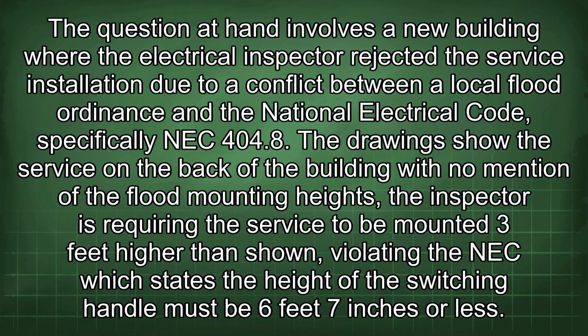The question at hand involves a new building where the electrical inspector rejected the service installation due to a conflict between a local flood ordinance and the National Electrical Code, specifically NEC 404.8. The drawing showed the service on the back of the building with no mention of the flood mounting heights. The inspector is requiring the service to be mounted 3 feet higher than shown, violating the NEC, which states the height of the switching handle must be 6 feet 7 inches or less.